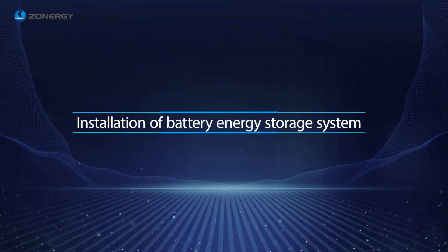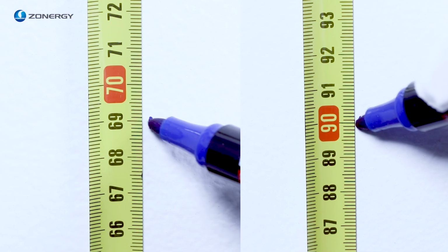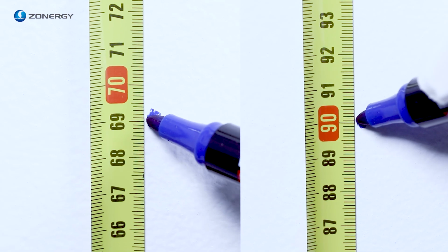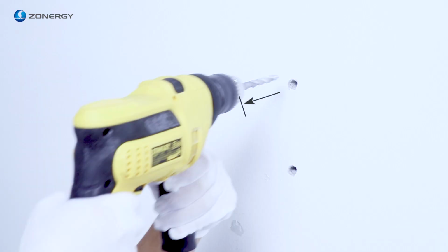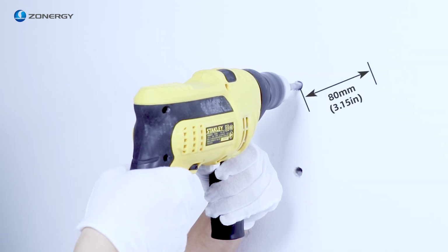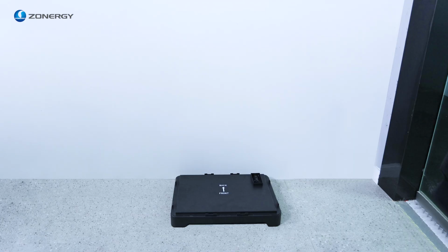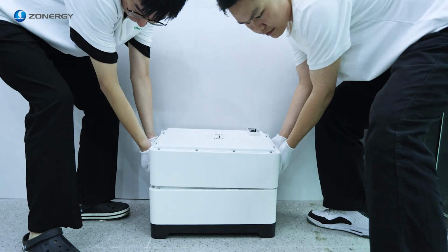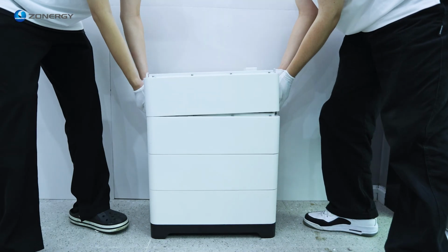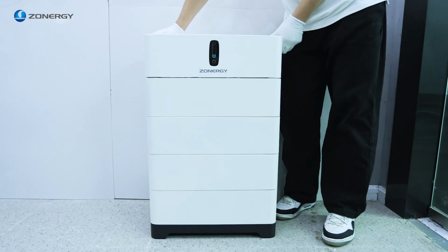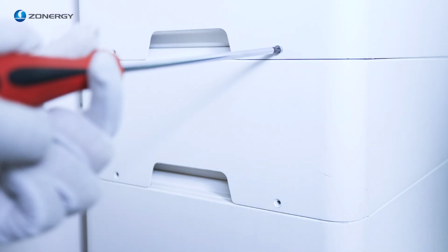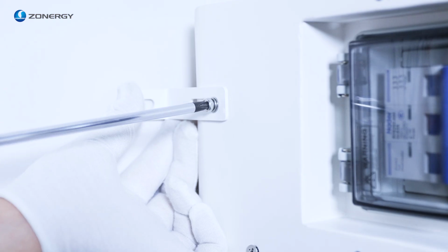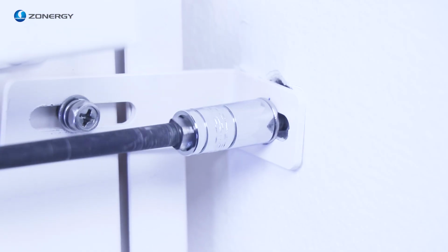Chapter 6 Installation of battery energy storage system. First, select the appropriate installation position and mark the corresponding points. Next, using a percussion drill with a bit diameter of 10 millimeters, 0.39 inches, make sure the hole depth is about 80 millimeters, 3.15 inches. Secure the battery base to the ground. Stack battery packs one by one and install the center control box at the end. Secure the battery pack and center control box one by one to ensure stable installation. Finally, attach the battery to the wall.